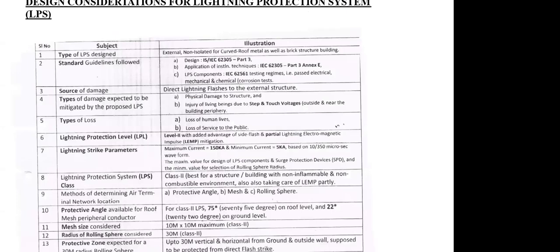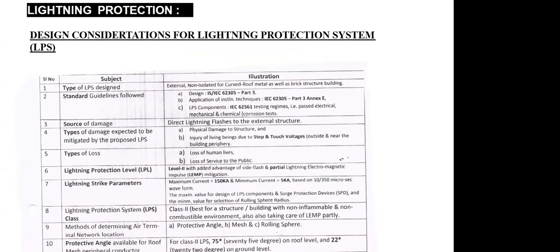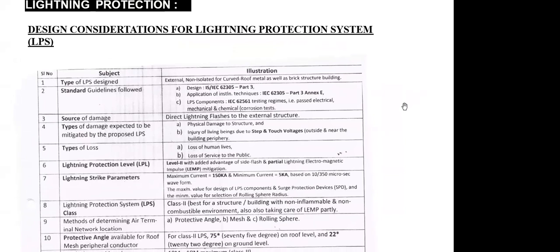Next comes the design consideration for the lightning protection system. I was going through an article some time back, and probably all of us know that there have been a lot of deaths in the last couple of months because of the rainy season and lightning. I think we had some 13 million lightning strikes in the last 4 to 6 months. So it is very important that we install a proper lightning protection system in any of our installations, whether it is a building, hospital, or any type of application.